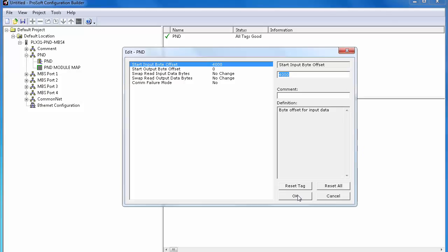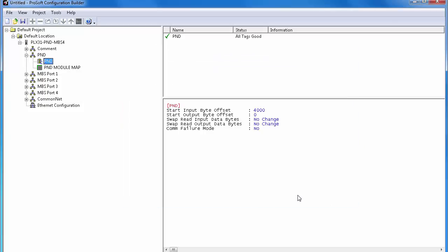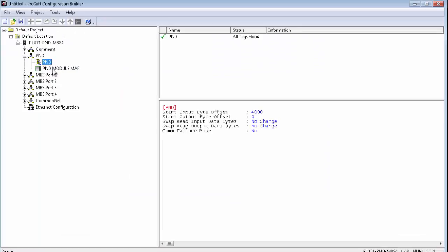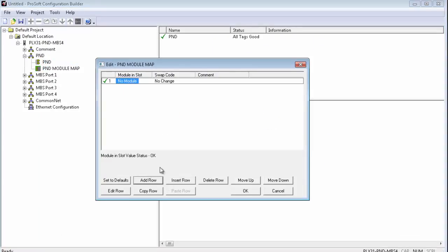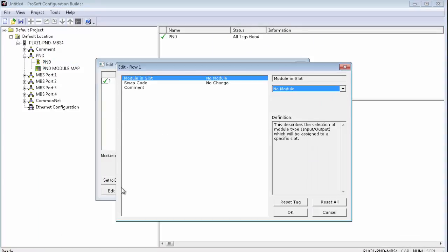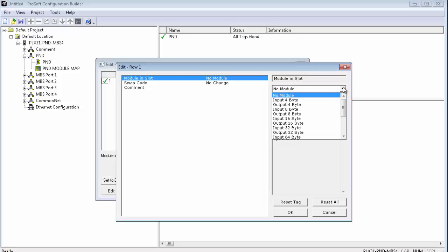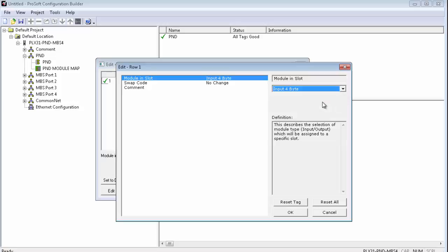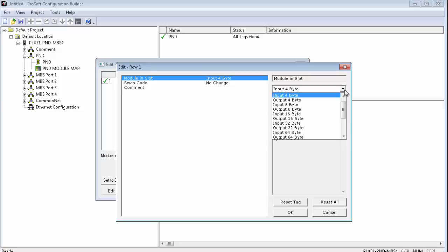Also, if you have to correct any byte swapping for the entire PROFINET network, you can do so here. I don't need to, so I'll leave all of this default. Next, click on PND Module Map. Right-click and choose Configure. We'll add a row and then edit that row. And here is where we will host and receive specific amounts of data for the PROFINET controller. Let's say a PROFINET controller needs to send us 4 bytes of data and receive 4 bytes of data.